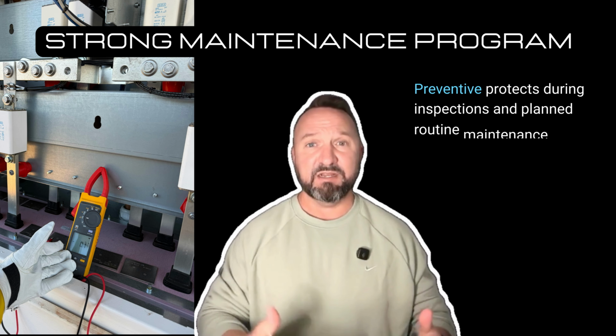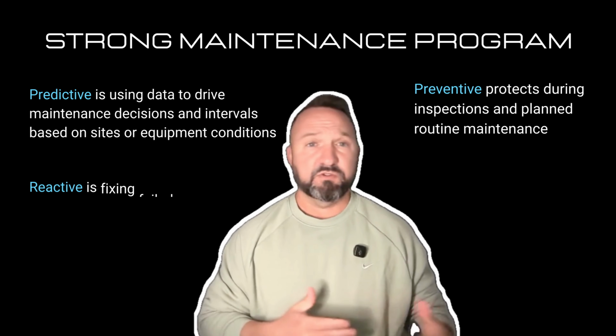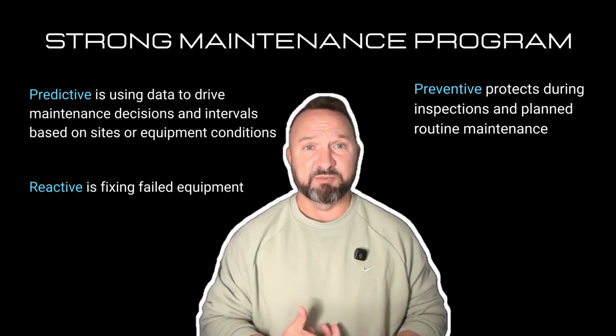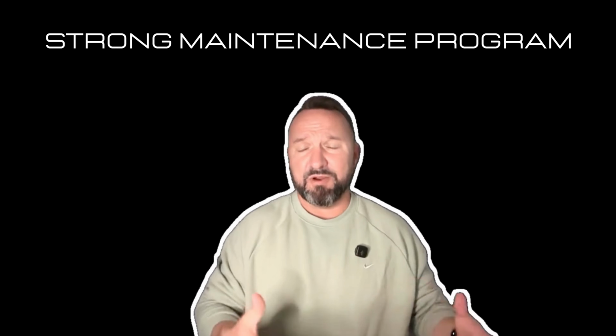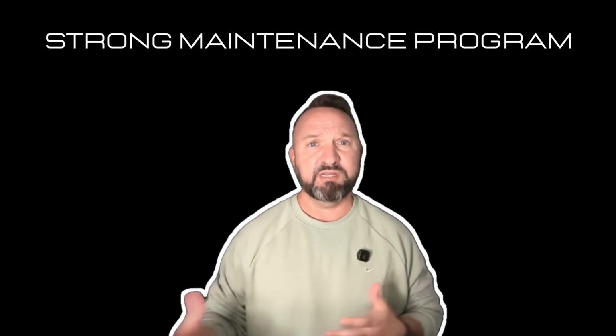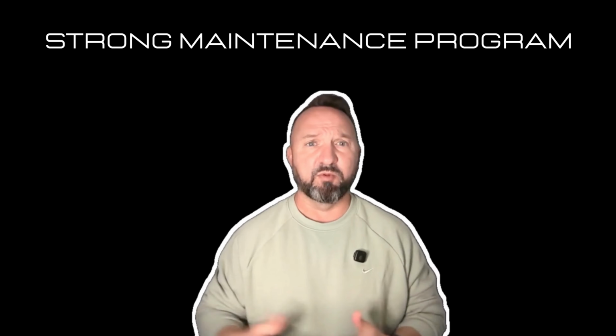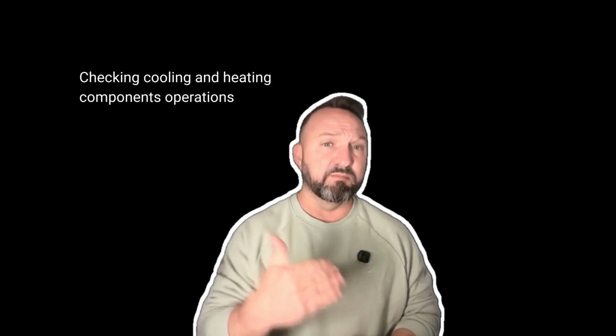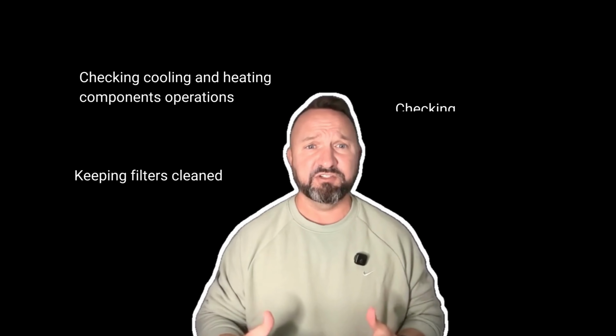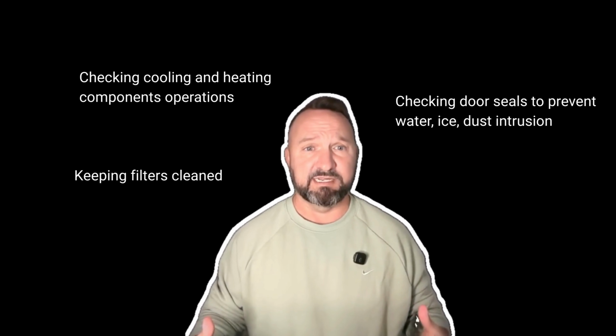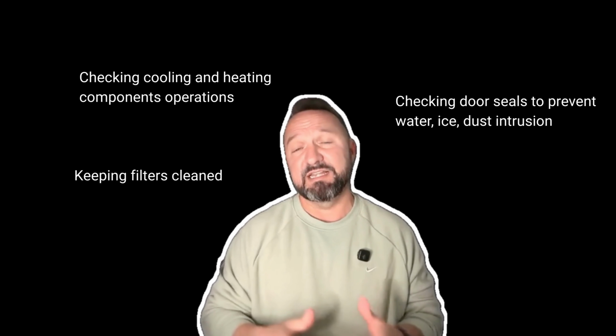All right, so the first defense against obsolescence, or equipment no longer being available, or spare parts issues, is really going to be strong maintenance programs. Good maintenance slows equipment degradation, extends the useful life, and allows for proactive identification of issues. For solar and battery sites, this is really going to include thermal management. Heat is the enemy of our electronics, and they're out in the elements. It's really hot, it's really cold, there's huge temperature swings. So, regular maintenance on the cooling and thermal management systems is going to be crucial for the life term of these projects. Cleaning inverter cooling systems, replacing air filters, inspecting fans and heat exchangers, and ensuring the proper airflow through our battery containers. This reduces the heat dramatically, which extends the life of our electronics.